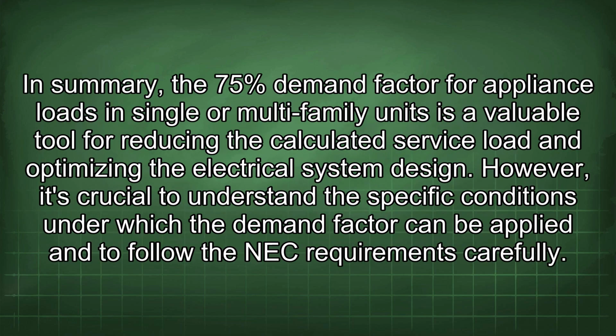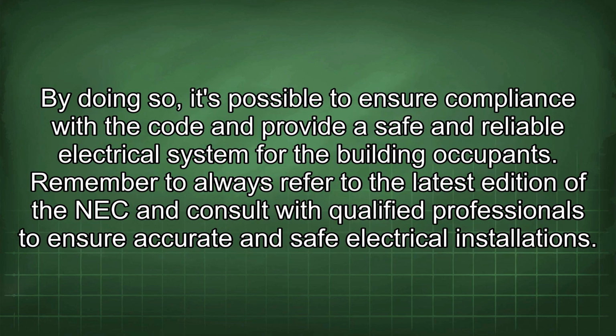In summary, the 75% demand factor for appliance loads in single or multi-family units is a valuable tool for reducing the calculated service load and optimizing the electrical system design. However, it's crucial to understand the specific conditions under which the demand factor can be applied and to follow the NEC requirements carefully. By doing so, it's possible to ensure compliance with the code and provide a safe and reliable electrical system for the building occupants.